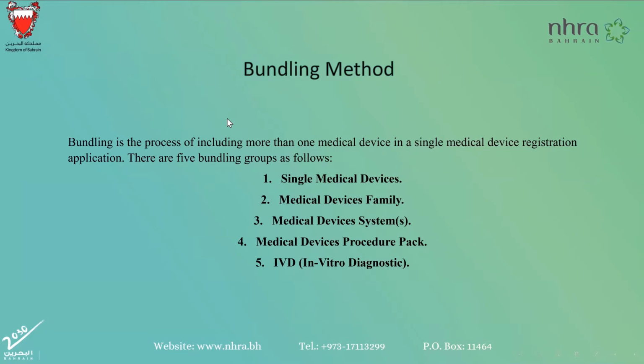Today we're going to talk about the bundling process and medical device registration applications. Bundling is the process of including more than one medical device in a single medical device registration application. There are 5 bundling groups: single medical devices, family, medical devices system, medical devices procedure pack, and IVD.